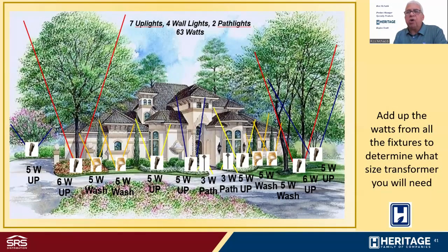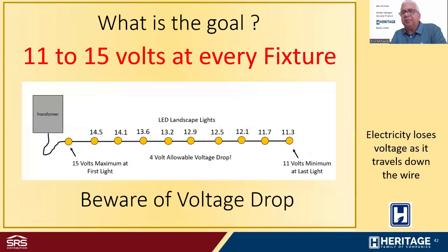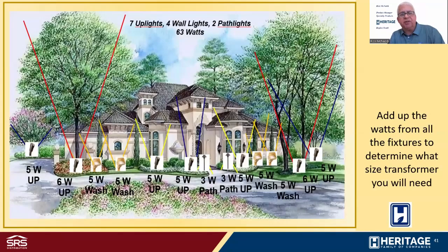So knowing the total wattage of the project helps us choose the transformer. Since professional outdoor lighting transformers start in a 150 watt capacity, I could put these 63 watts of fixtures on one 150 watt transformer. Once I decide that I'm going to use a 150 watt transformer on my 13 fixtures, I have to think about what my goal is, because you can see here in this diagram, I've got fixtures going all the way across the front of the house. I'm going to have, looks like about 100 something foot of wire running from the transformer to all the fixtures. So to make this system work properly, I've got to accomplish a goal.